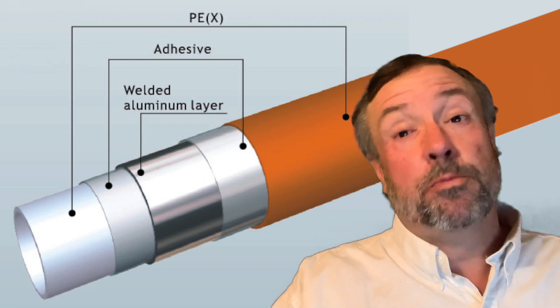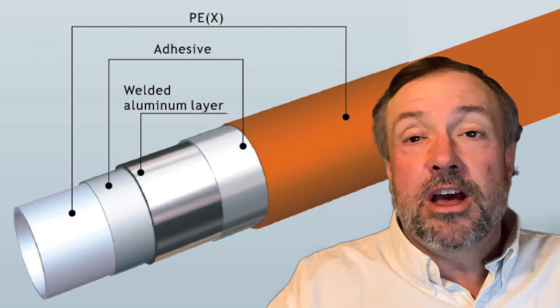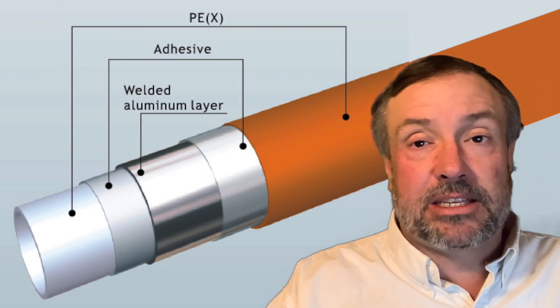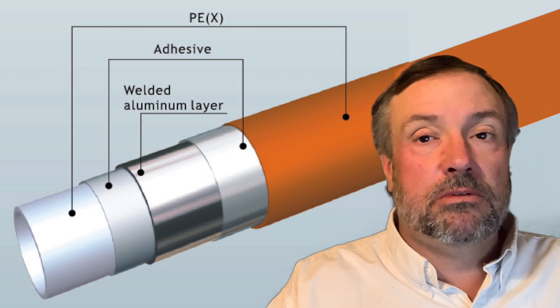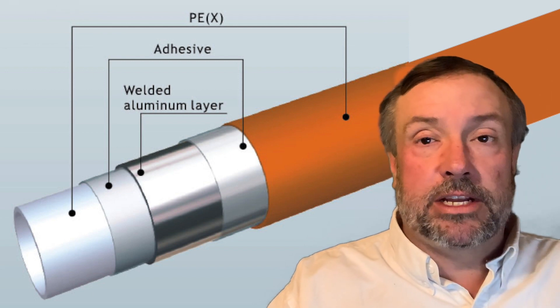There is a super PEX and I like to call it a super PEX. It's not running around with a cape on or anything, but what this type of PEX does is it can get you a lot closer to 100 degrees Celsius with a liquid. It's called Aluminum PEX. Basically what it is, is PEX that has an aluminum covering over the plastic, which allows it to handle a lot more heat. And as a side effect, if you've ever had to lay PEX on the ground, you know it bends and flops and goes all over the place. But Aluminum PEX stays in place.